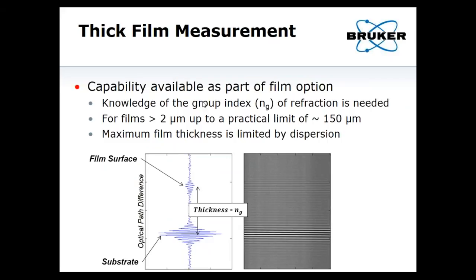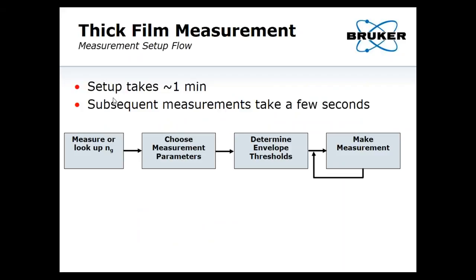Here's how you actually do the thick film measurement. You'd see two sets of fringes on screen, although you generally want to null these out before you actually do the measurement. What do you need to know? You need to know the group refractive index, and that's about it. You have to set some envelope thresholds. Setup takes about a minute. Subsequent measurements only take a few seconds — however long the VSI measurement that you programmed actually will take to run, maybe one to three seconds.